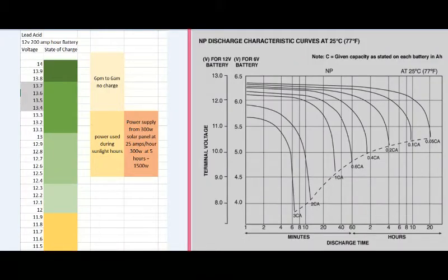This next chart we're looking at here is a relationship with usage management in a solar system. The charge state on the left, you really can't expect to get anything from the 14 down to 13.7. As soon as it stops charging and the battery goes to rest, it's actually charged at 13.7. What's important, and no one ever talks about in designing solar, is your usage. If you'll notice over to the right, it says 6 p.m. to 6 a.m. no charge.